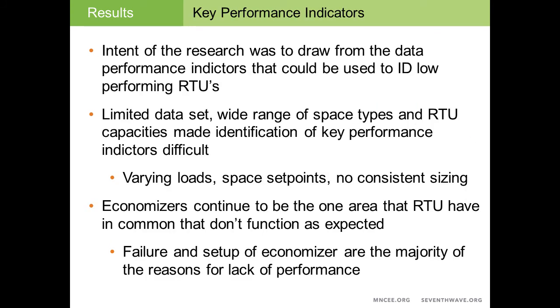So lastly, we wanted to try to tease out performance indicators from this data. And the reality is that we didn't have a lot of performance indicators that we could get from this small sample set. There was a wide variety of space types, a wide variety of RTU capacities. This made it very difficult to identify a key performance indicator. Space set points were changing, and the capacity per area of floor area shifted quite a bit between sites. So I think one of the takeaways is it's very difficult to identify a key performance indicator from a rooftop unit because there's no consistent application for rooftop units at a wide variety of sites.